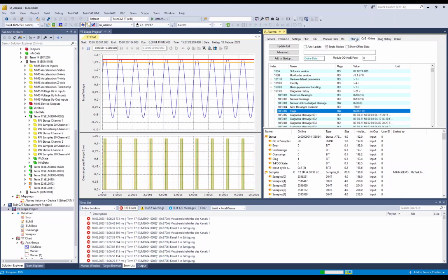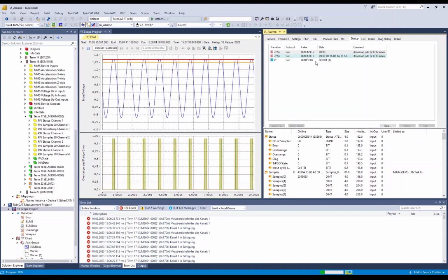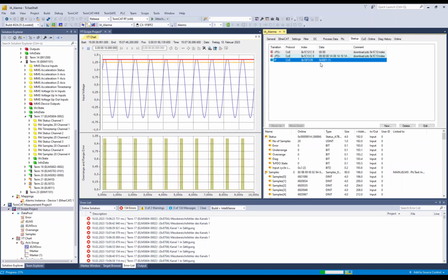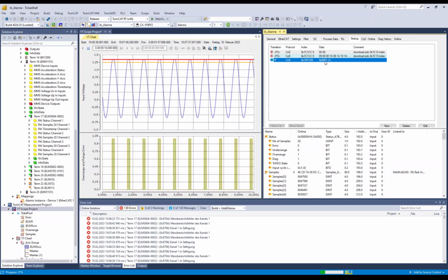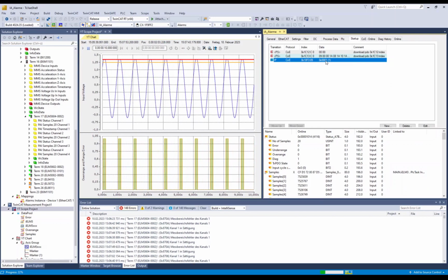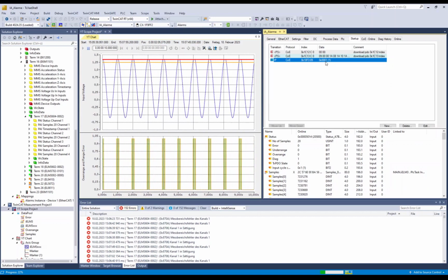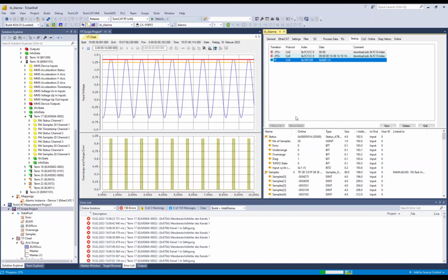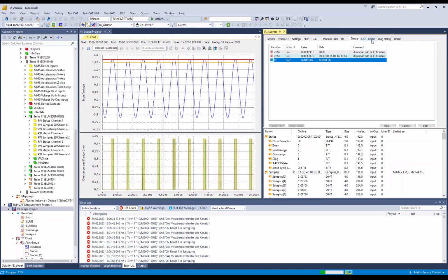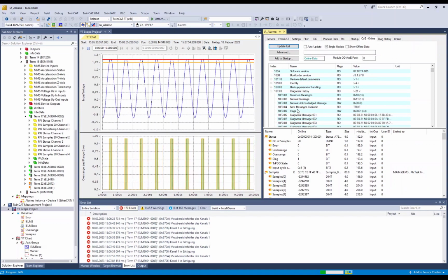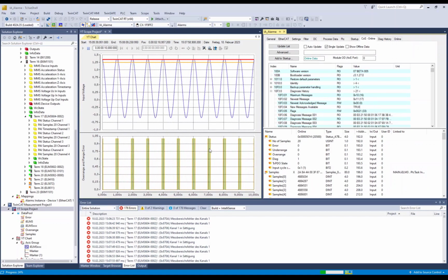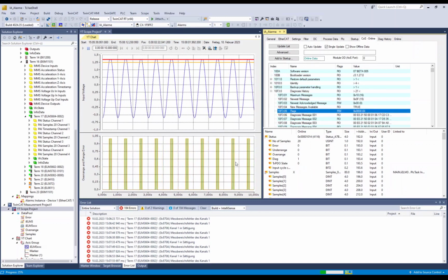All the ELM terminals have a startup command. So initially, when you add this to a TwinCAT project, you will have this enabled by default. So with setting this to 0, you can eliminate this automatic error logging here. But the best thing is just to leave it as it is and to control this in the COE with setting the flags to 0 or 1, whether you need an error list or not.